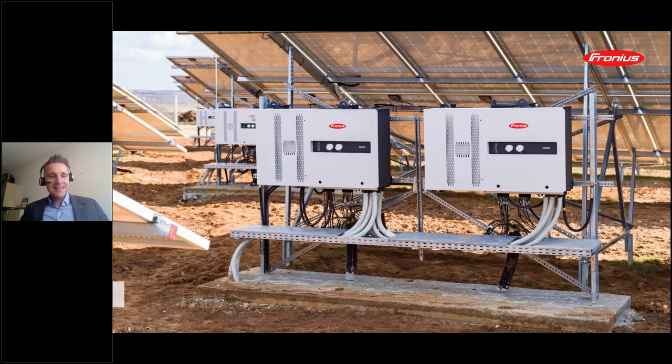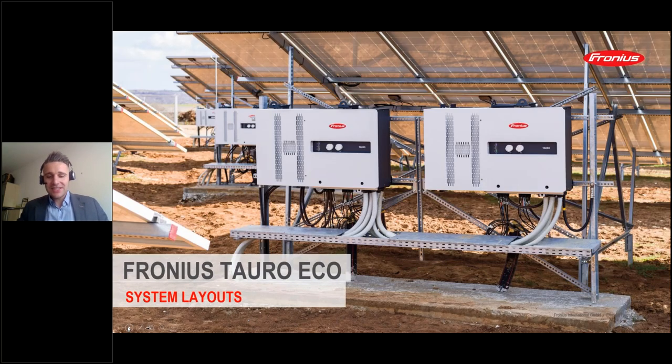Yes, that was the power stage exchange of the Tauro. Like you see, very, very easy. I think it can be done within a few minutes. And that's also a key argument, of course, for the Fronius Tauro, this service topic, service in general for Fronius, very, very important. We really have this concept of service on site, no inverter exchange. And that's possible due to this power stage system.